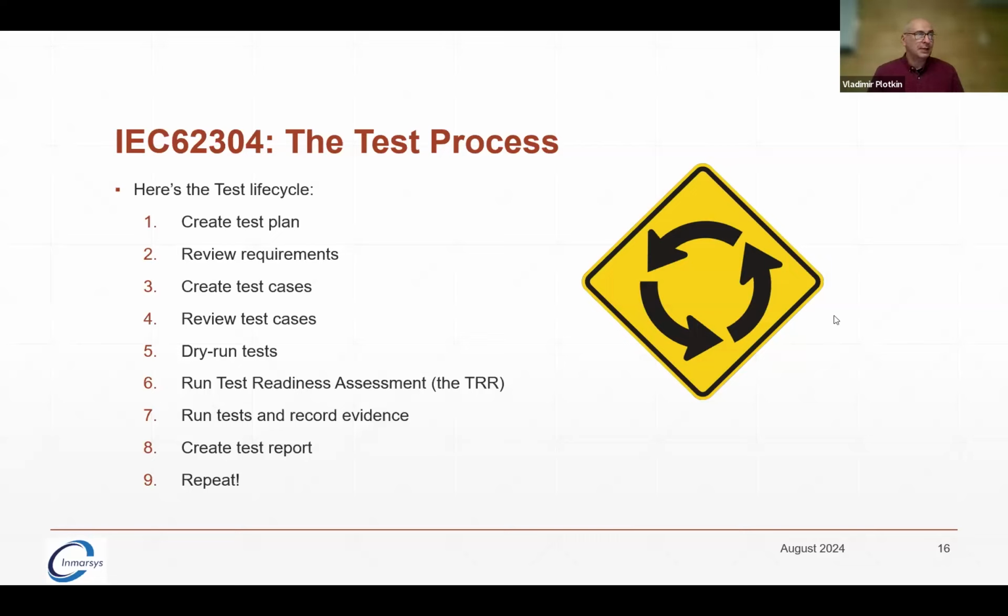Then they run the test readiness assessment, which is not strictly speaking required by the standard, but it's a good practice to have. It's basically a checklist. Can they do the formal testing? Do they have all the hardware? Do they have all the software? Do they have all the documentation in place? So is everything there to enable them to run smoothly through the process rather than stumbling at every single step? And then they create the test report and then they repeat, because the work never ends. So they restart with each new release.